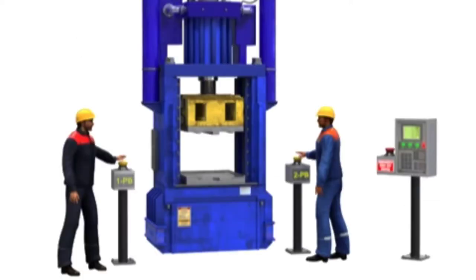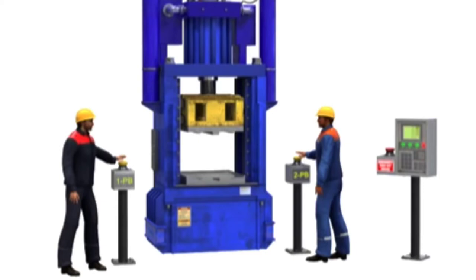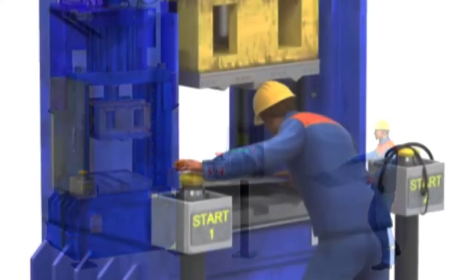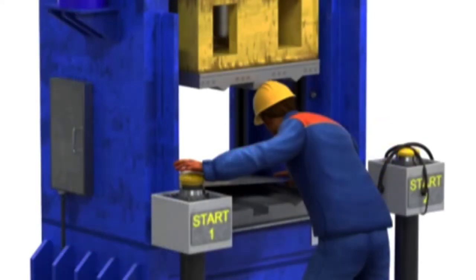While two-hand controls wired in series is ideal for machines with two operators, it becomes unsafe when only one operator is present. Although two buttons are still required, it becomes much easier for a single operator to tie or weigh down one button, allowing unsafe operation. To prevent this unsafe condition but still permit a single operator, anti-tie-down circuits are employed.